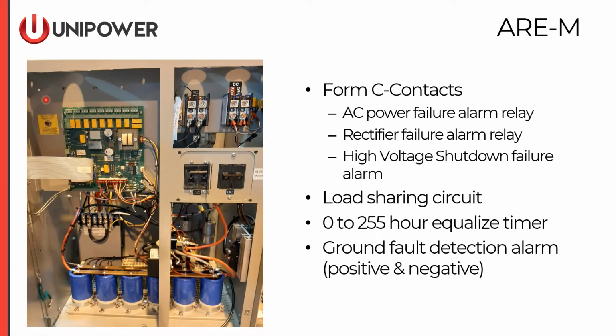Equalize timer is a standard feature for all ARE-Ms. It can be set to 0 to 255 hours, and it can also be set to automatically equalize. If a battery manufacturer recommends automatic equalize, it can be set to automatically equalize some batteries every couple of weeks, for instance. Ground fault detection alarm, again, is always included. The standard interface, as well as the alarm interface, can additionally be ordered with a ground fault detection disable switch, which allows an operator to disengage our ground fault detection circuit in case there's already an external ground fault detection circuit deployed, or when troubleshooting a ground fault, it's useful not to have a ground fault circuit in play while the troubleshooting is being performed.